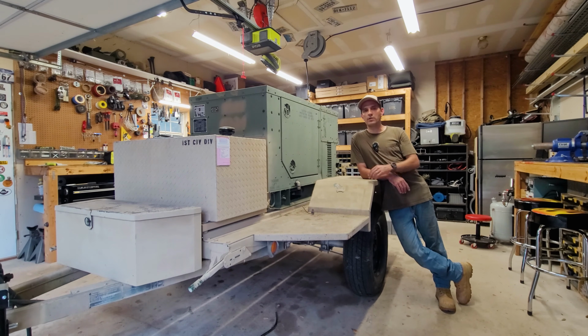And then taking apart your grounding rods, I already explained taking it out. But if you made it through your 6 hour load test, the only other thing is don't get to 6 hours, open your contactor and shut it off. Open your contactor after doing the opposite of what I did at the beginning. Slowly take your load off if you can. Go from full load and every 5 minutes take one piece off till you're down at like 0.